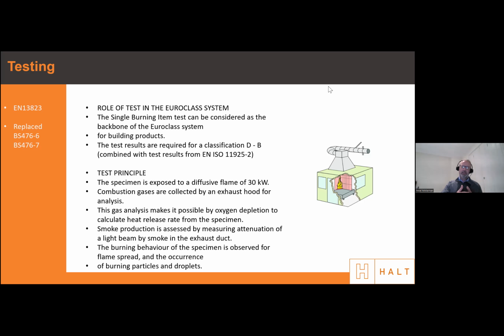All these things are critical to ensuring that any product introduced to the construction sector has been tested accordingly, and we're looking at the material itself and assessing its contribution to the fire, not just a fire retardant product that may be applied either on top or during impregnation. The material itself needs to be assessed for its own contribution to that fire, the amount of smoke, the gases produced, and the behavior of the specimen itself. Because even though 13823 replaced BS 476, which used to look primarily at spread of flame, we now need to consider materials used in construction for their reaction to fire and how much they contribute to the overall development of a fire.